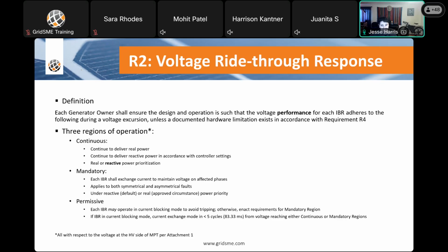And then permissive region. This is just for really low voltages. Each IBR may operate in current blocking mode. So this is momentary cessation to avoid tripping. Otherwise, just enact the same requirements for the mandatory region. Now, if the IBR does have current blocking mode, there is a requirement that once the voltage stabilizes on the high voltage side of the transformer, current exchange mode needs to be entered within less than 5 cycles.